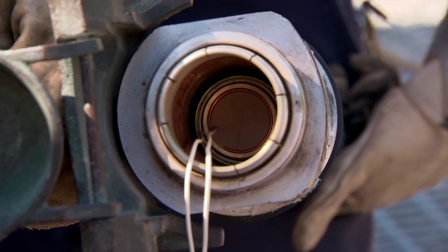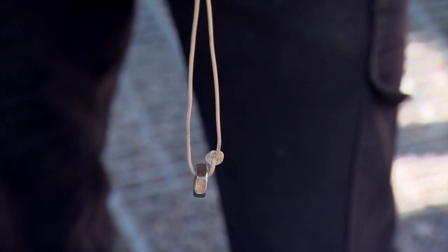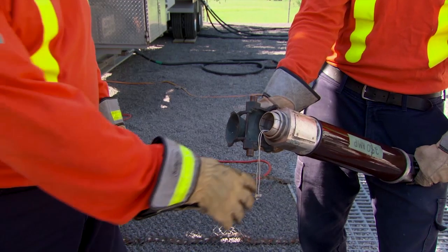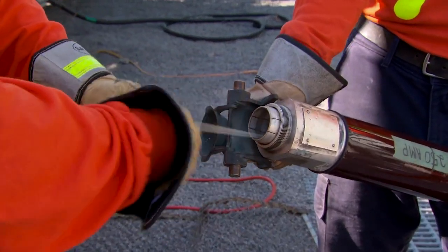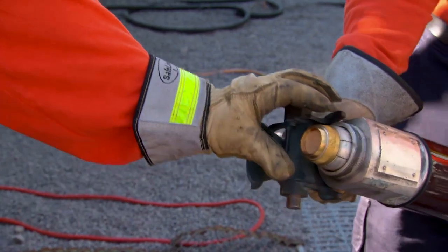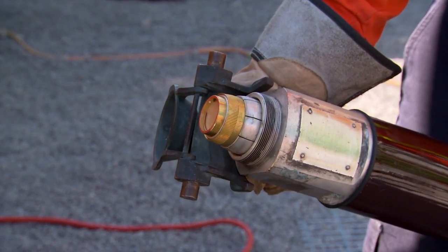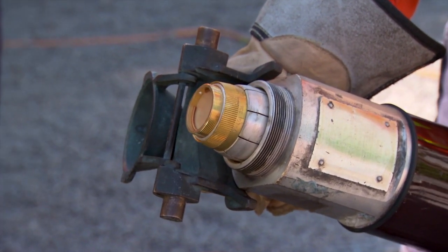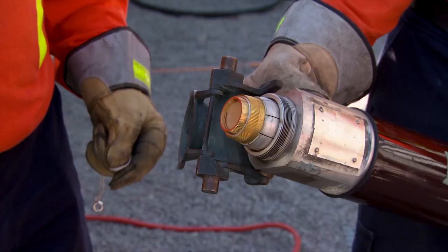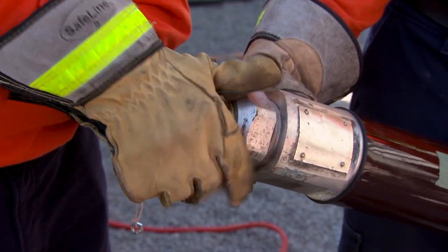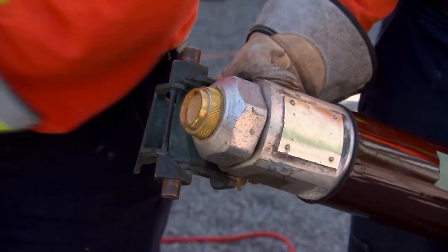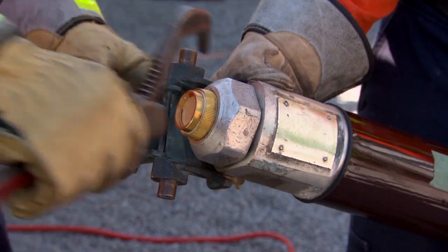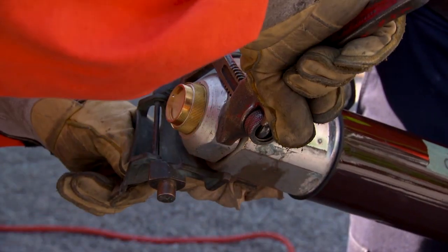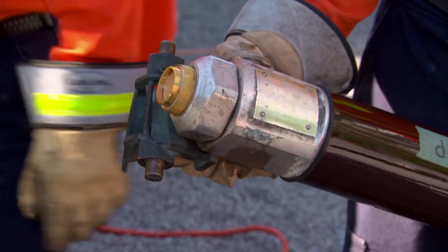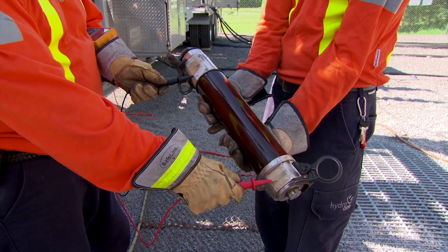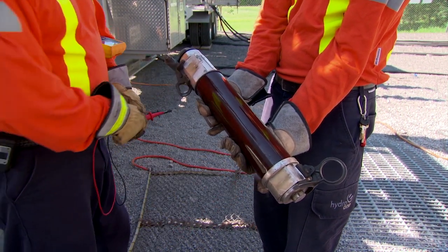Turn the fuse over and firmly pull the fuse through the locking ring using the string. This should be done with 2 people. Remove the string if it doesn't break. Tighten the retaining nut. Retest the fuse for continuity with a multimeter and label the fuse with the proper rating. Install the newly prepared fuse.